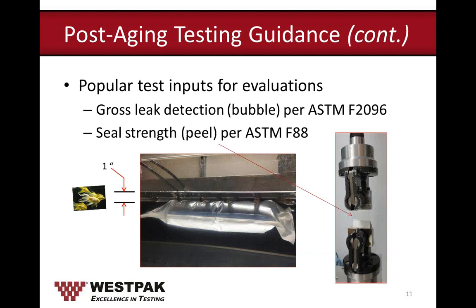The popular test methods for these evaluations include gross leak detection, to ensure there are no holes or leaks that would allow microorganisms to pass through and contaminate the sterile device. This looks at the whole package. In the picture, you can see a pouch submerged under one inch of water — if there is a leak, you will see bubbles forming. To be considered a leak, it needs to show a steady stream of bubbles.